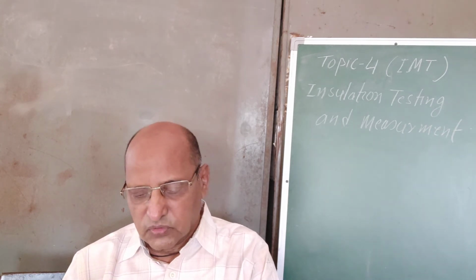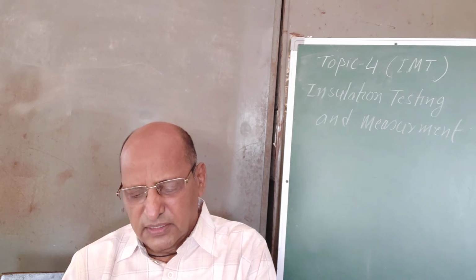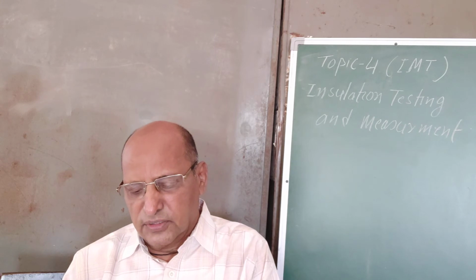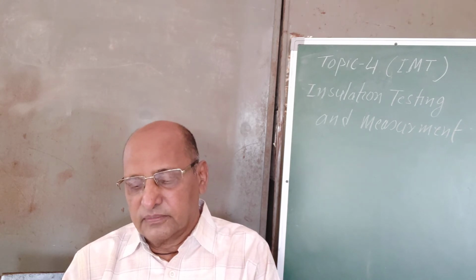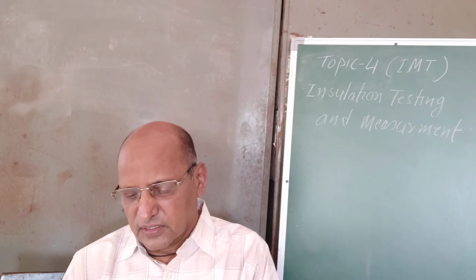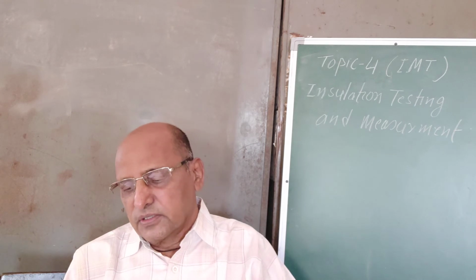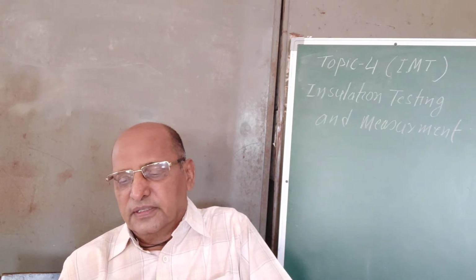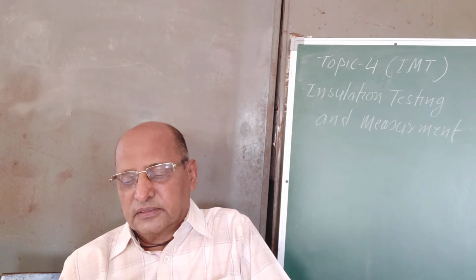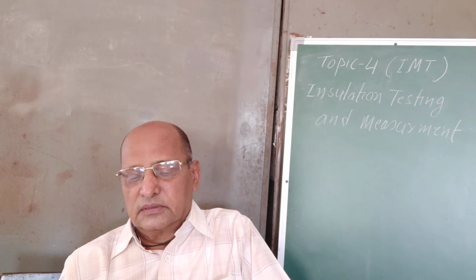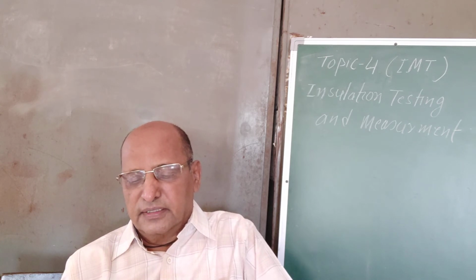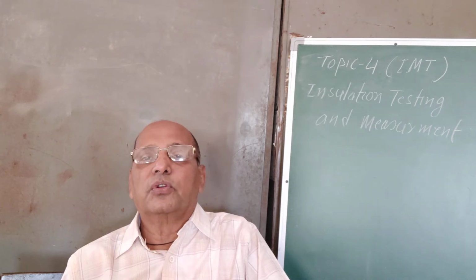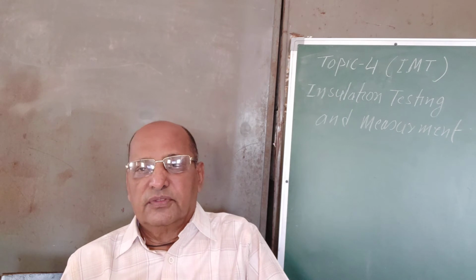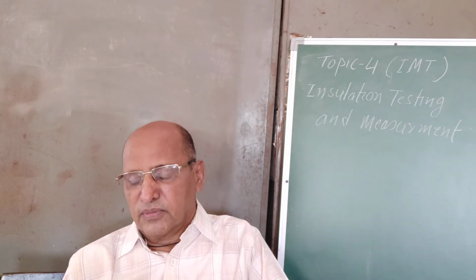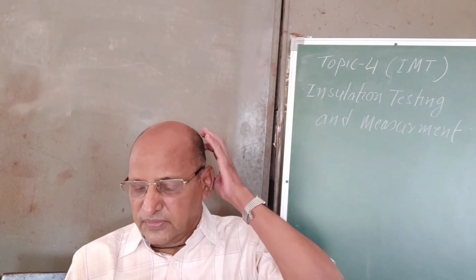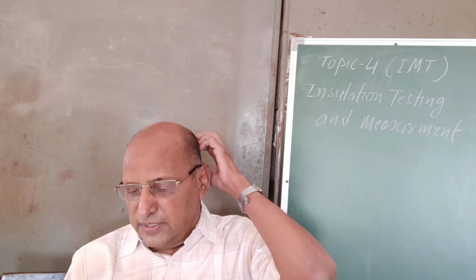They are about 12 to 14. So normally you have to memorize all these values according to their standards, so that a pure oil which is under working condition should have these types of readings for the different properties. As I have told you, we require measurement of the temperature of the winding, that is the internal temperature of the winding. I have already told you that for winding temperature measurement we use the pyrometer or infrared thermometer, so that from a distance you can measure the temperature of the winding.